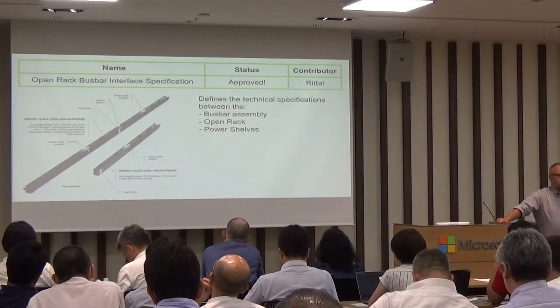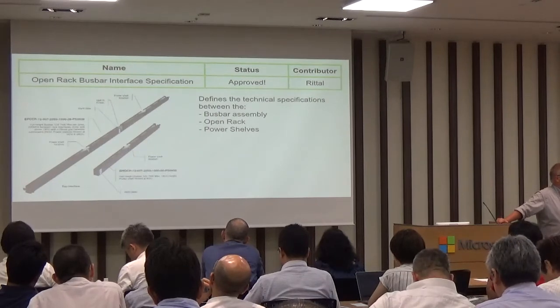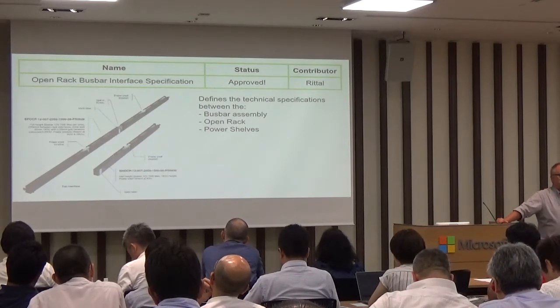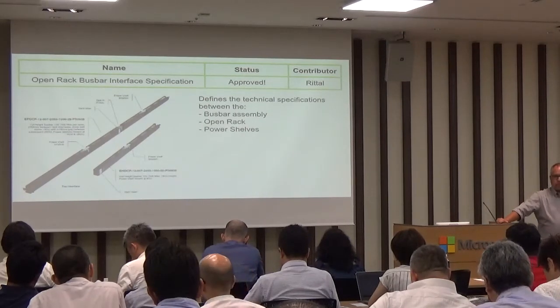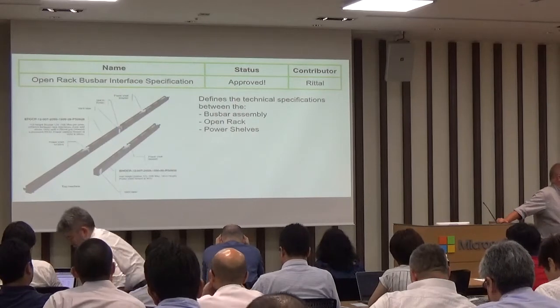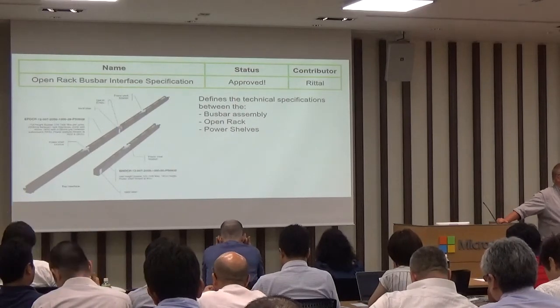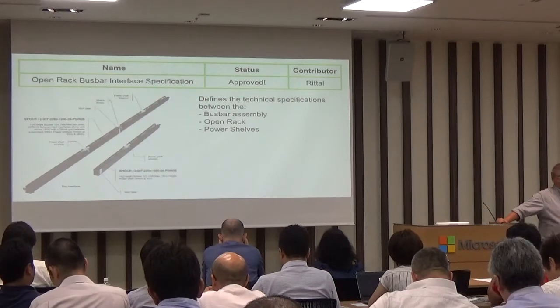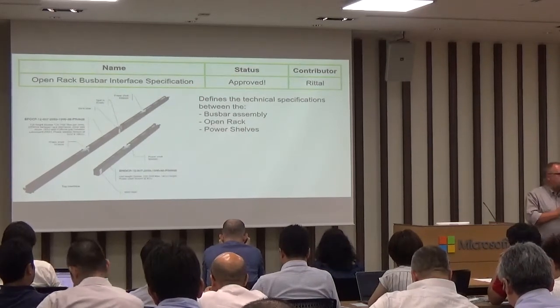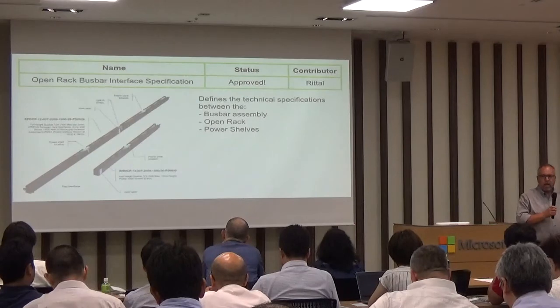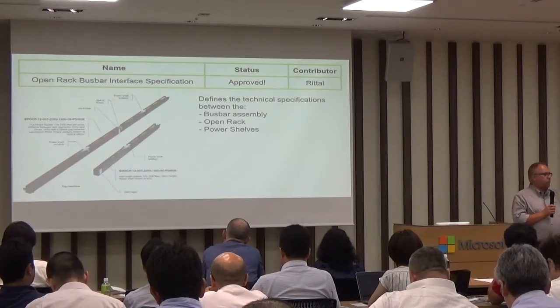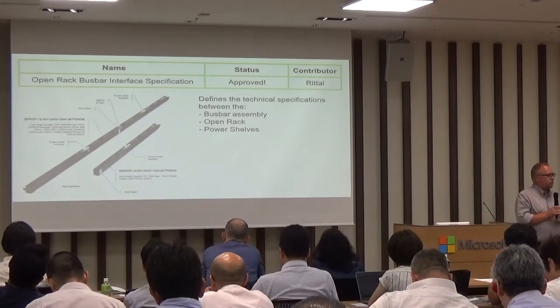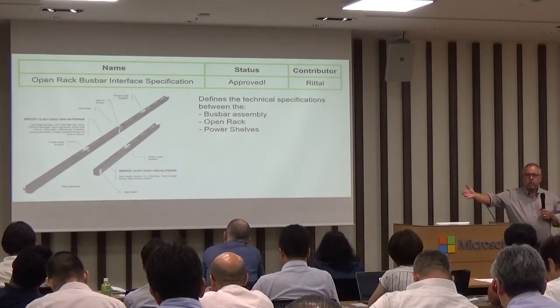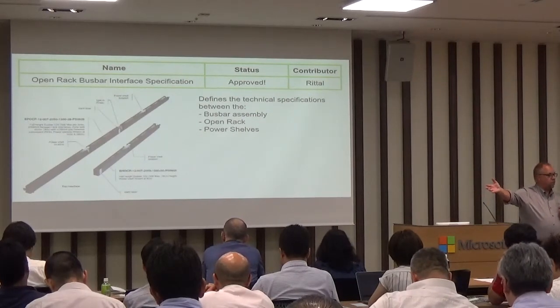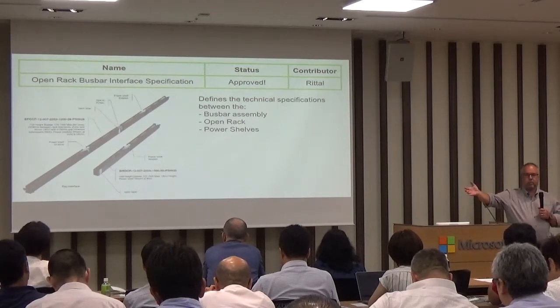Why is that important? Think about the supply chain and where those racks can go. If you have any experience with co-location facilities, you know not all co-location facilities share the same power densities. So if you go into facility A, you may have a rack designed for, say, 4 or 6 kilowatts of power. If you go into facility B, you may have the opportunity to put in 12, 15, or 25 kilowatts worth of equipment.